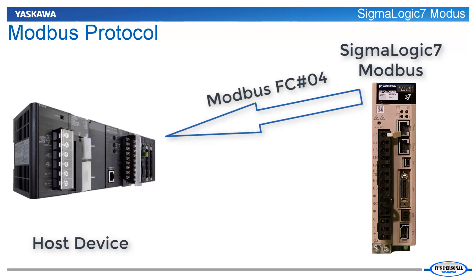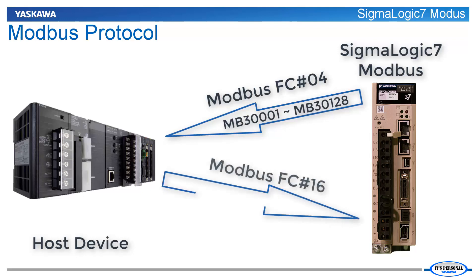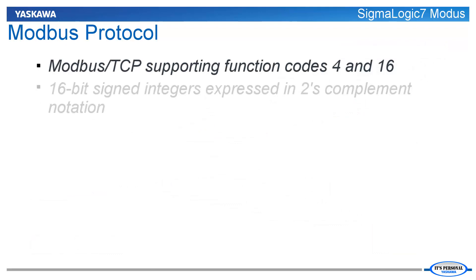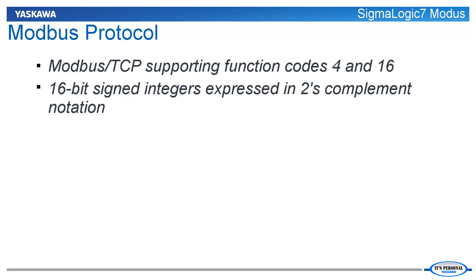The product supports Modbus function code 4 to read input registers 300001 through 300128, and function code 16 to write multiple holding registers 400001 through 400128. Data is sent and received by the Sigma Logic 7 Modbus as 16-bit signed integers using two's complement notation. It also stores its data in little-endian format.